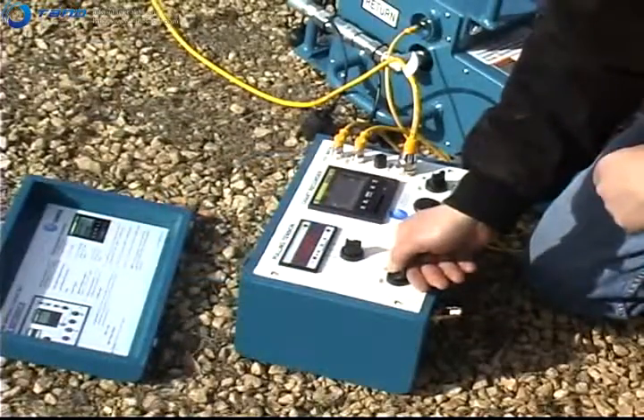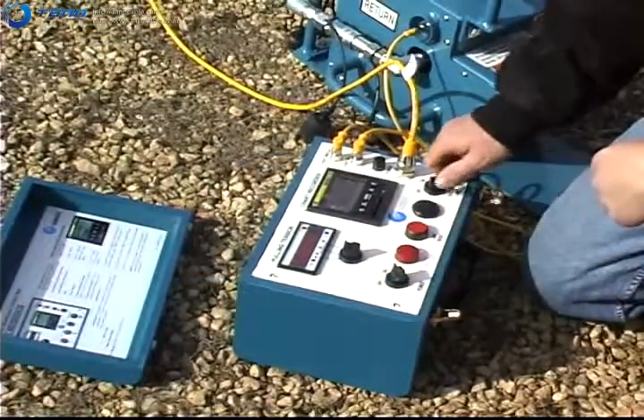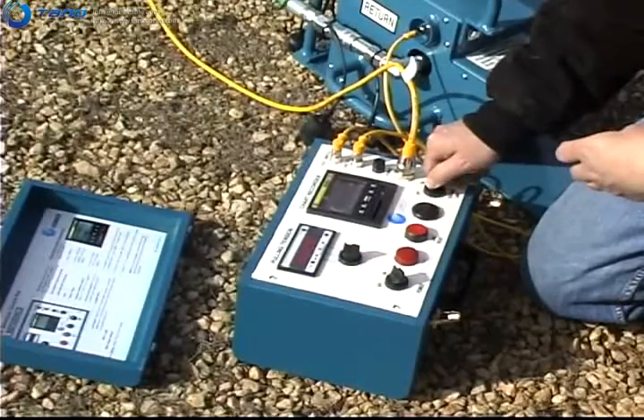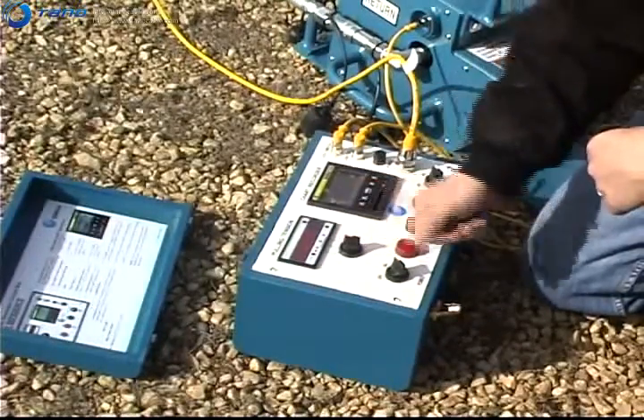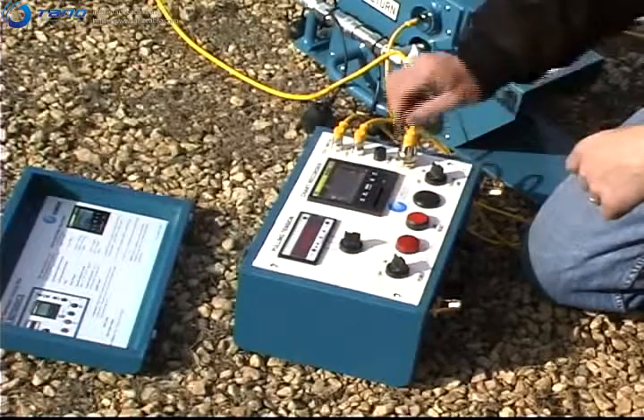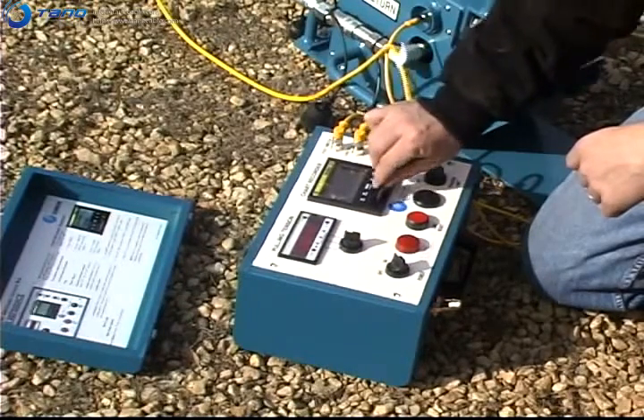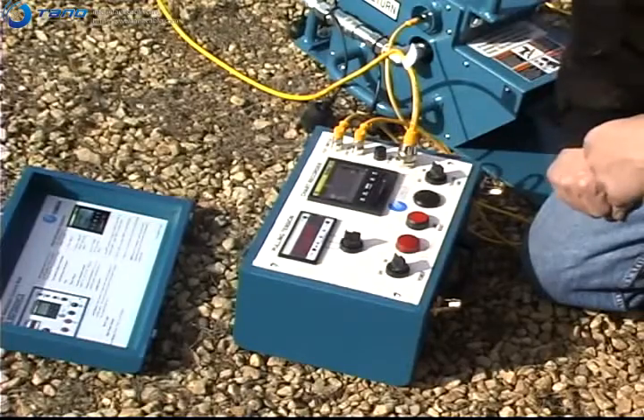When the electronically programmed tension overload limit is set higher than the adjustable relief valve, the puller will stop when the relief valve setting is reached. If the pulling operation exceeds the electronic tension limit or relief valve setting, correct the cause for high tension.